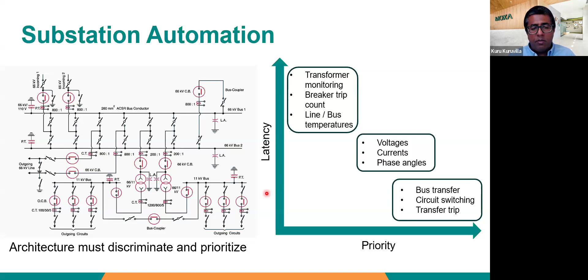On the other end of the spectrum, you may have things like bus transfer, where you're transferring load from one bus to another, or operation of breakers. Those are directly tied into reliability or safety, and those actions must take place immediately. So the critical aspect is that the architecture you put in to automate the system needs to be able to discriminate and prioritize.